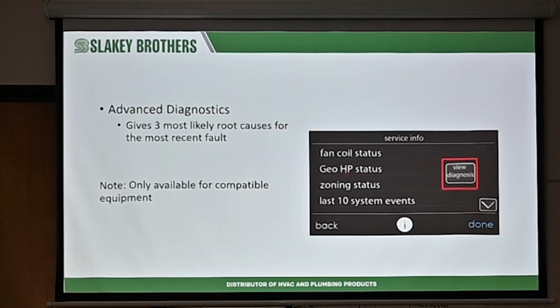I hate this screen because of this geo heat pump status, but let's just say this is a fan coil status, a regular heat pump status, zoning status, and this one here is the important one: last 10 system events. It's not error codes yet. The second page, which we'll see in a second, is. But for the last 10 system events, you press it, and some of it might just be information that it's giving you.